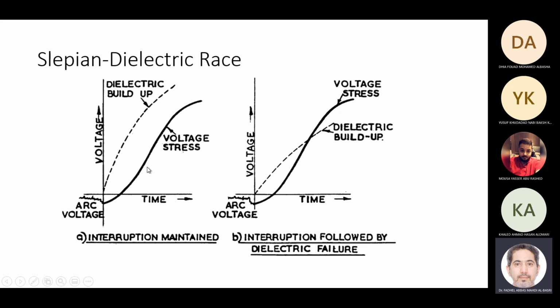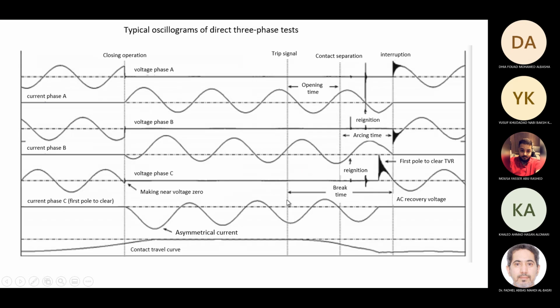So this will be a successful tripping or clearing of faults, while here at this point there will be a failure. The breaker will not extinguish the arc after this point. This is just an illustration of a breaker being initiated to close operation at this point.